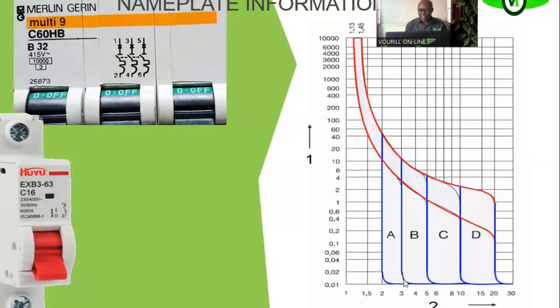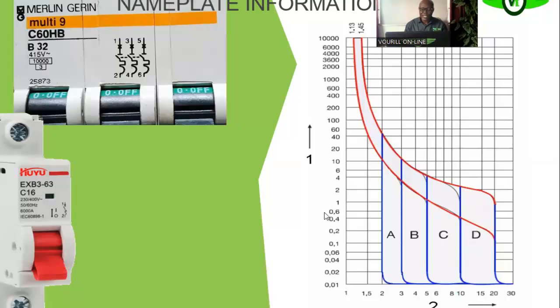The horizontal axis shows multiples of the nominal current rating, while the vertical axis shows the time scale — how long it takes the circuit breaker to trip in seconds. So for this B curve circuit breaker, it will trip instantaneously when current is between three and five times the nominal. When the load is 32 amps or less, the circuit breaker operates in the safe region and can operate indefinitely without tripping.